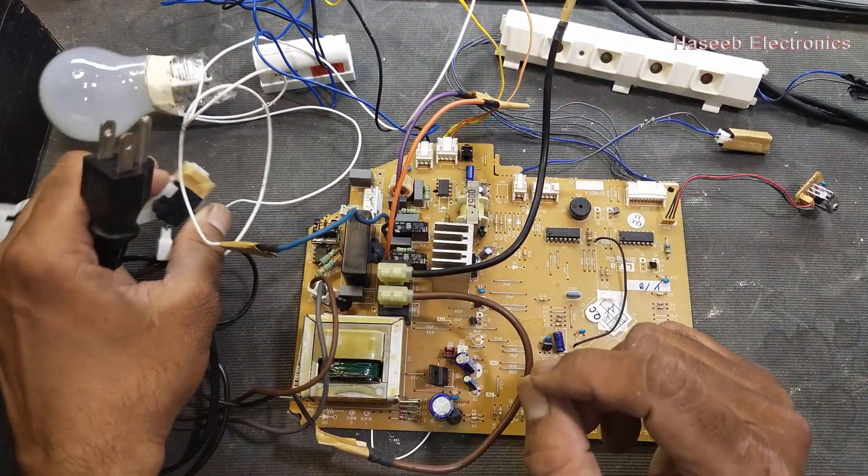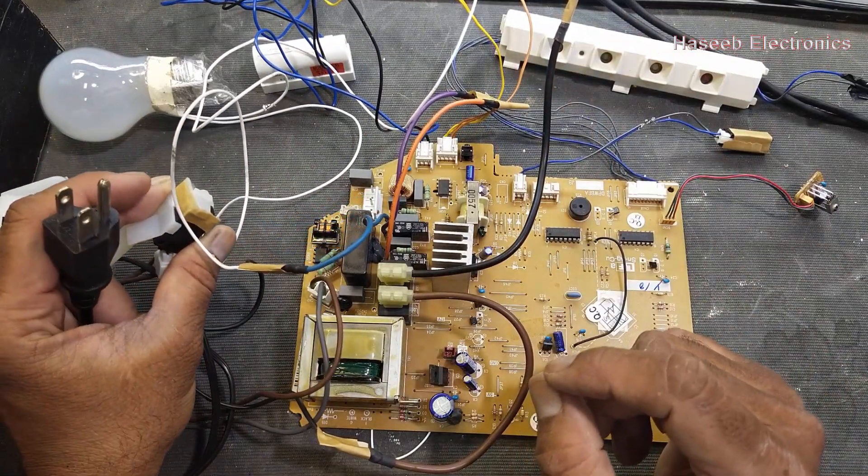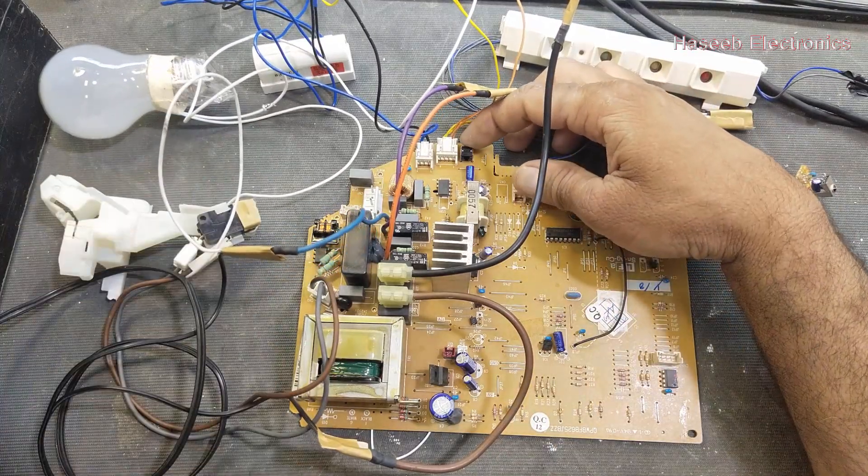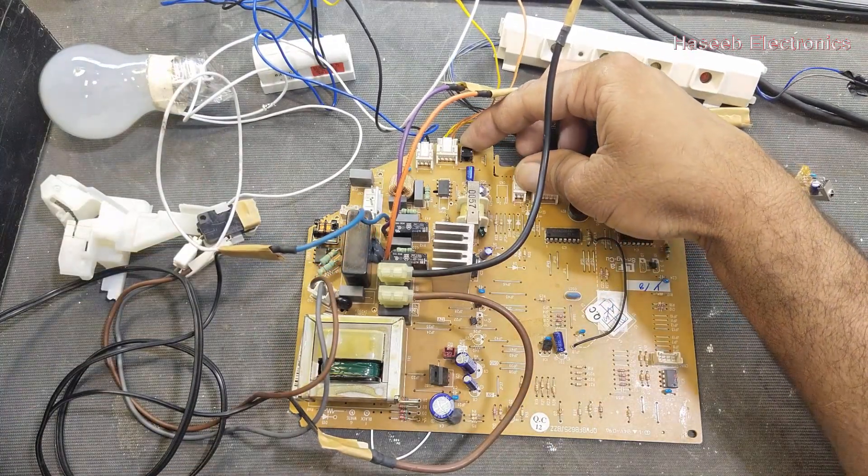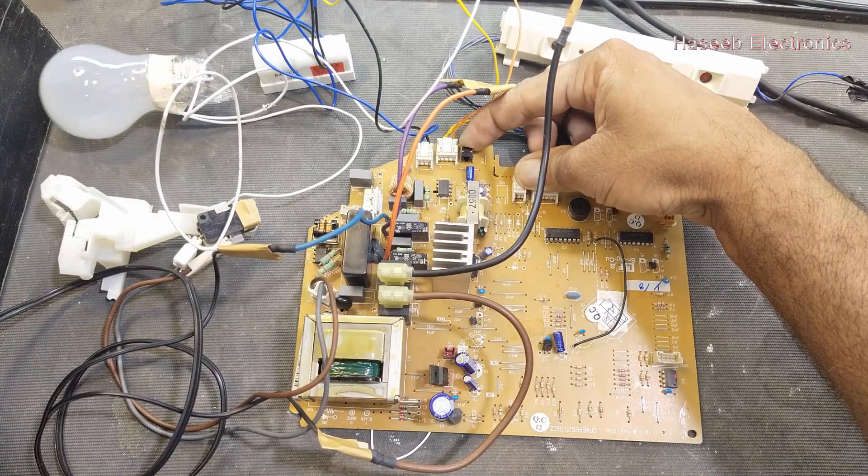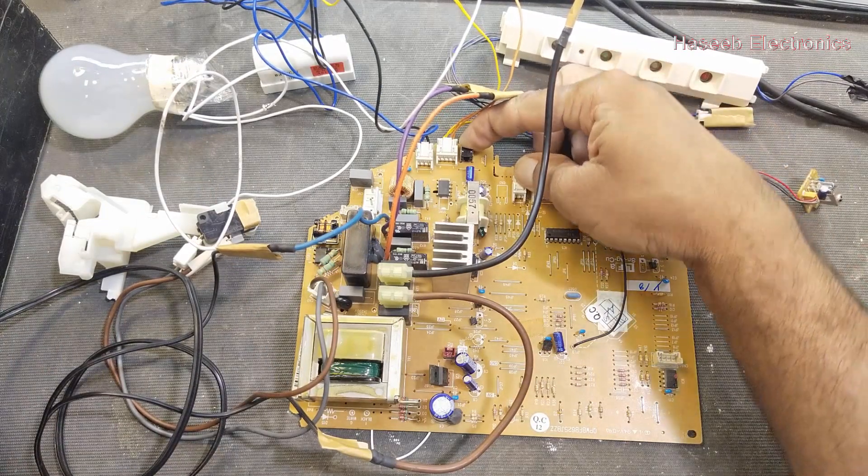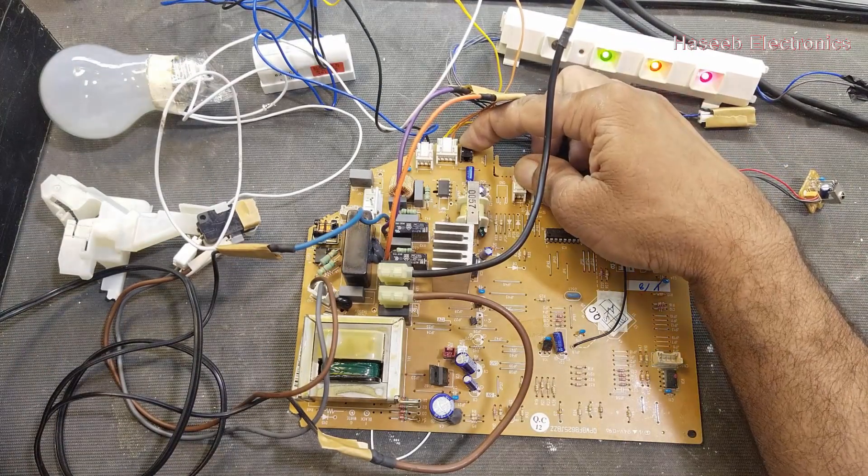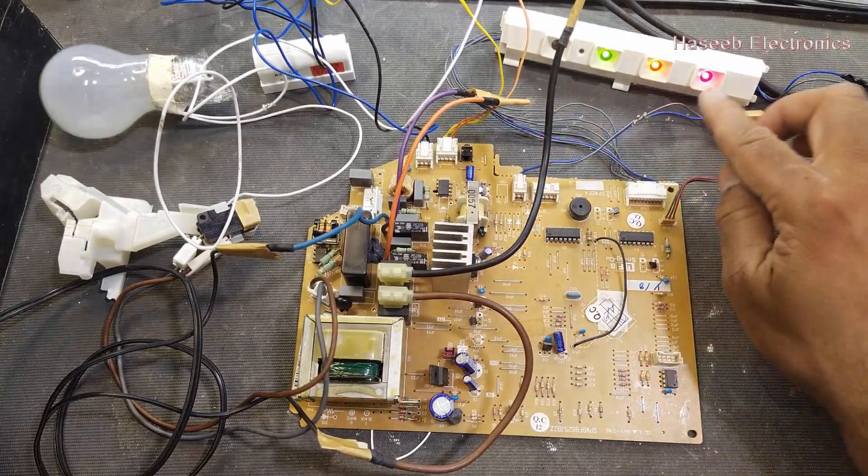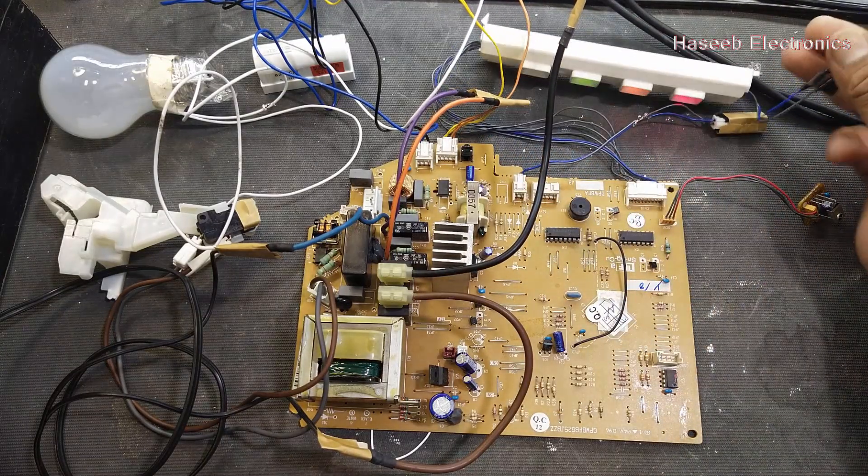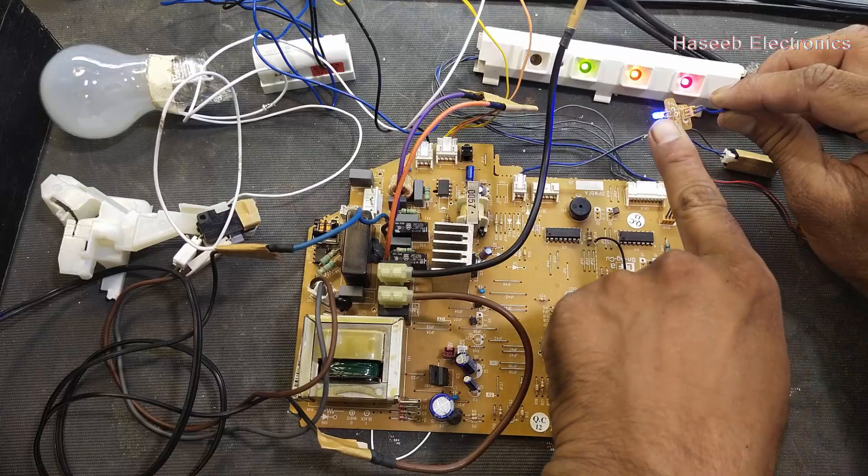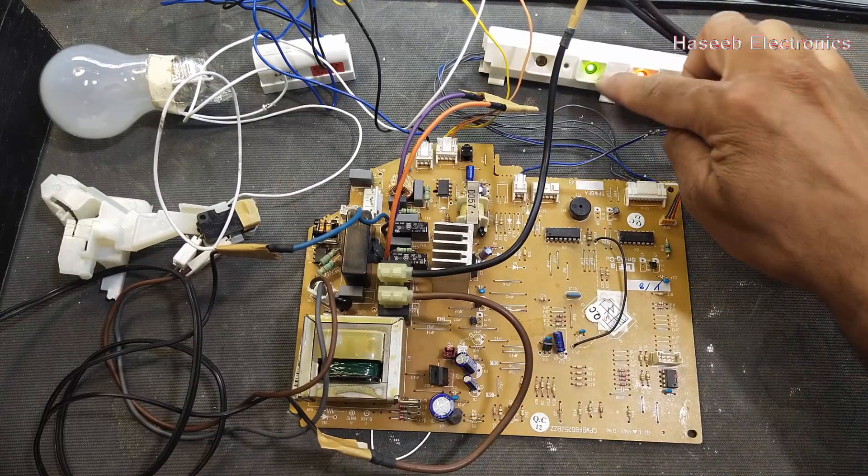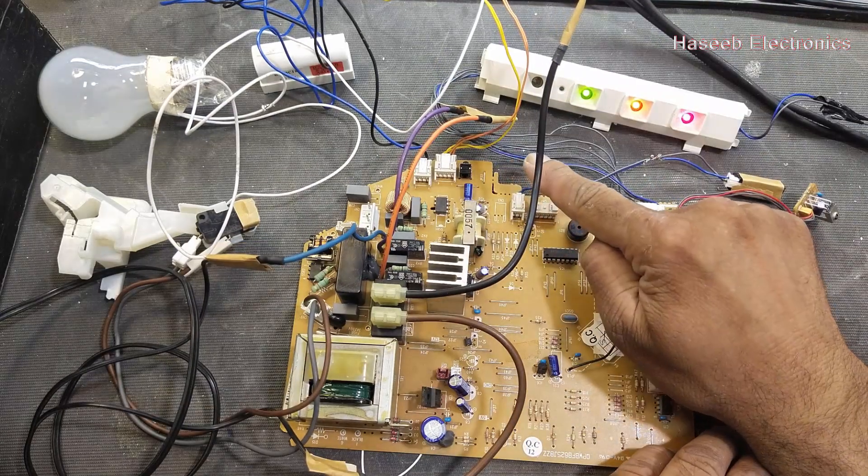Now press this button, our this switch test switch is bypassed. Press this button, reset button, and apply power 220 volts. After five seconds, these four LEDs should glow. One, two, three, four.